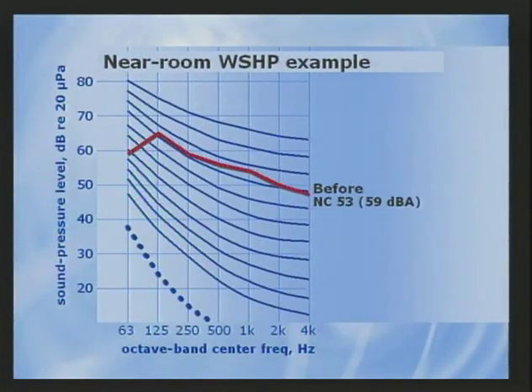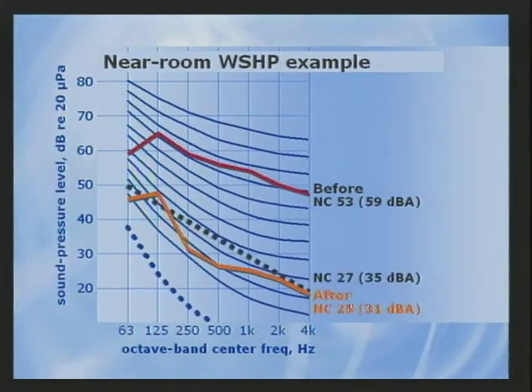Placing the unit over the space resulted in an NC53, 59 dBA sound spectrum. Not quite as bad as the example we saw earlier from the Ohio school study, but still well above our target. The changes that were made bring the overall level down to NC25, 31 dBA. This is below our target of 35 dBA, but remember that we're only considering the HVAC contribution to the background sound. We also have to consider the sound from other sound sources that impact the room.